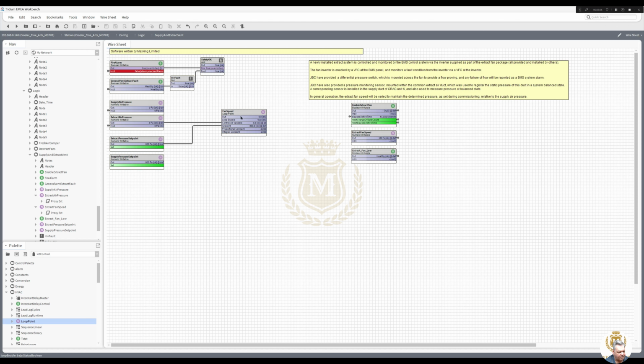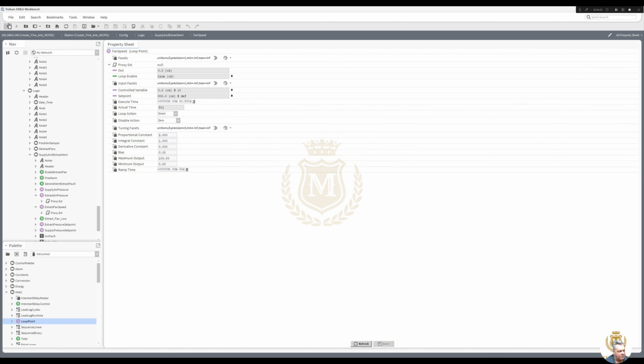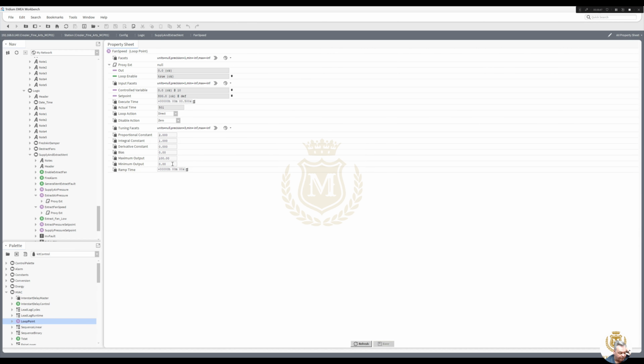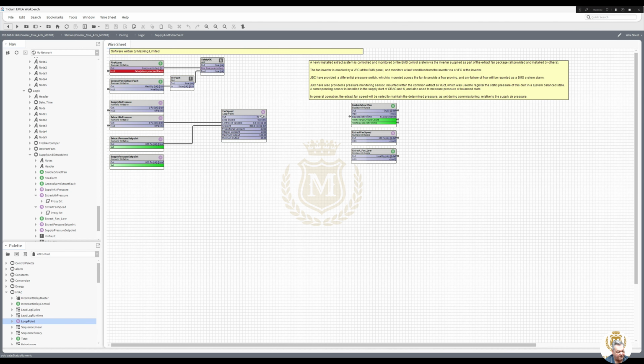And we need a minimum speed. So that's maximum and minimum. Maximum can stay as it is, but I'll still expose a point. Pin slot. Maximum, minimum. And we'll put in a minimum speed of... 50% is going to be 25 hertz. 20 hertz is normally the minimum, so we'll put 40%, so it can't go below 40% when enabled. Change the output to percent. And I'm not interested in a decimal place. So that's my fan speed.